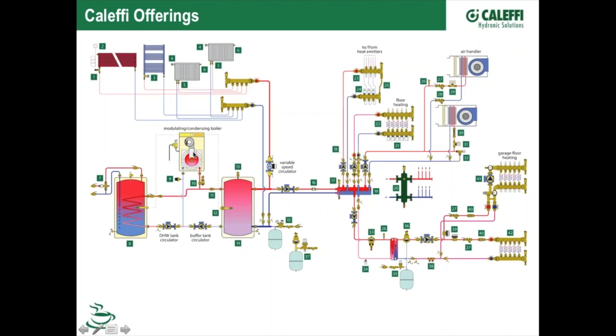That doesn't necessarily protect the rest of the components in the system. By using a flow switch like that, or you could have both of them in there, what this could do is you could wire everything in this drawing through that flow switch. So if you want the pumps to shut off when there's a low flow condition, it can drop off the signal to the boiler, the power to the boiler, as well as shutting off the pumps. Where the pressure switches in the boiler sometimes will only shut off the burner, and you can still have a problem if you're running pumps and you've developed a leak and leaked the fluid out of it.